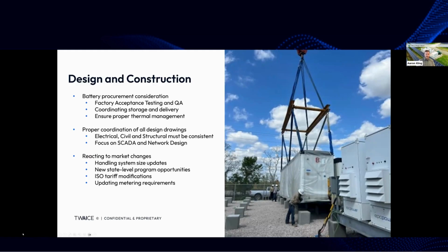We really want to see that coordination happen prior to construction. Sometimes I see the SCADA and network design still getting worked out during construction, and that almost inevitably leads to extra conduit needing to be run that wasn't originally designed for.